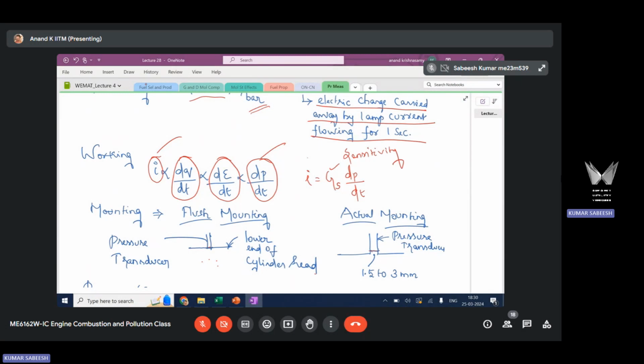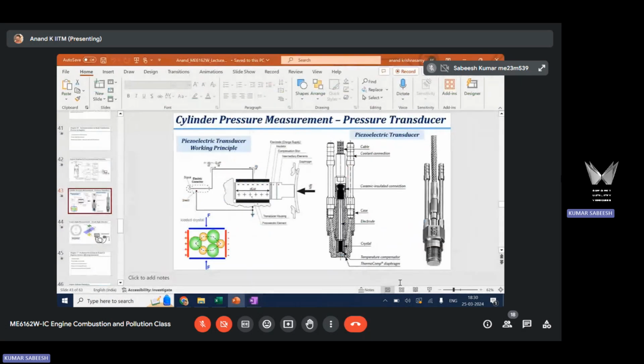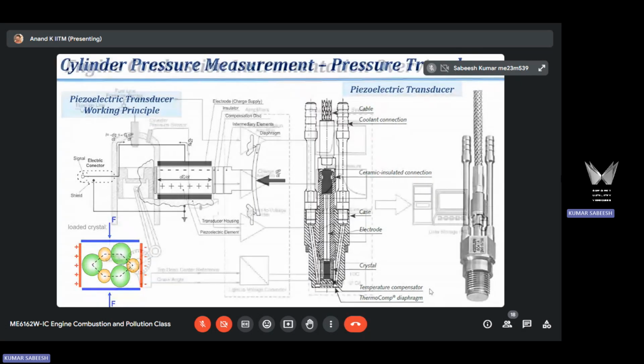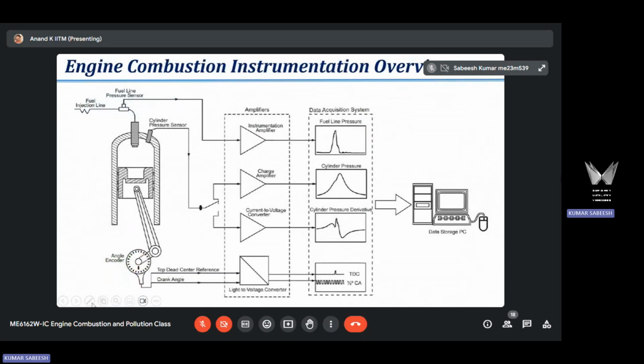So we are tracking this I that flows in the external circuit. From here it goes to this. You sense the pressure in the cylinder, it generates a current, and this current goes to a charge amplifier which amplifies the signal at the input and produces an output signal which is correlated with the in-cylinder gas pressure, right? This output is an electric signal which is correlated with the in-cylinder gas pressure. This is how you connect this electric signal output to the input. Input is the pressure inside the cylinder.